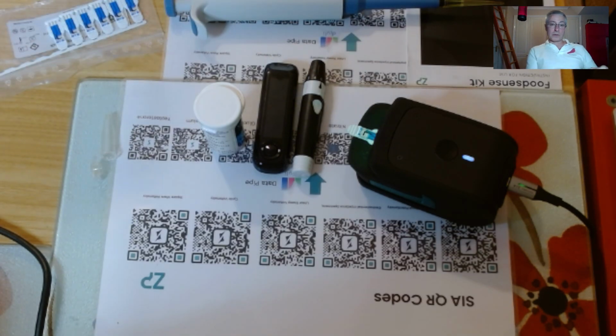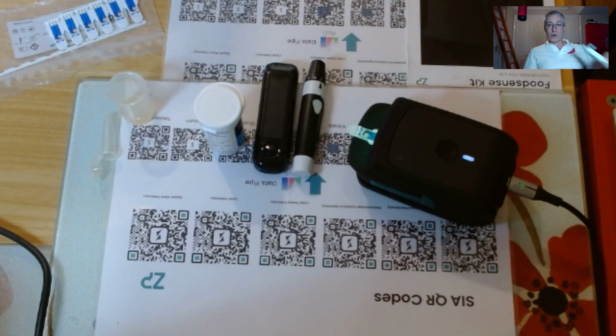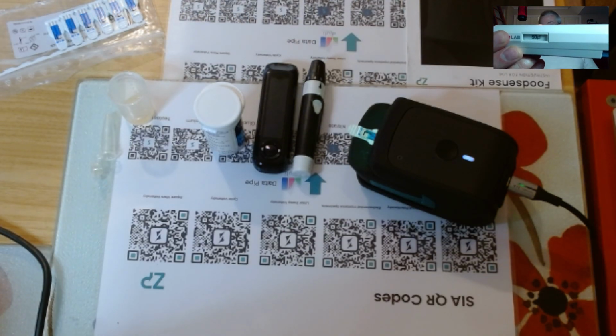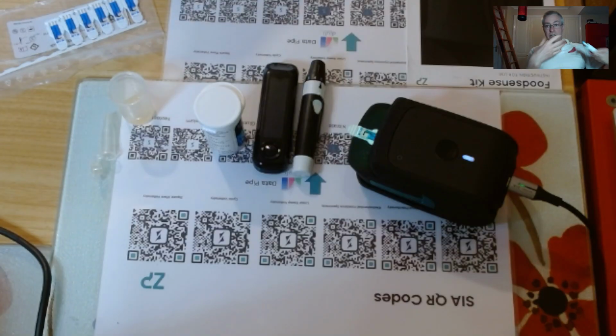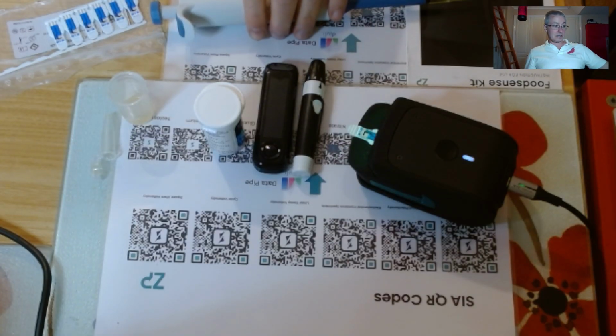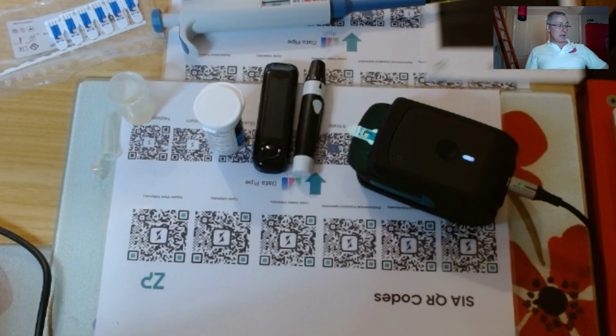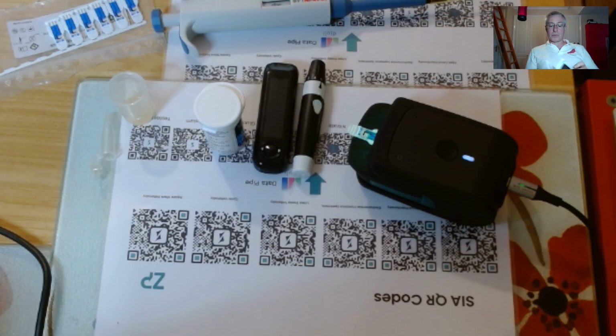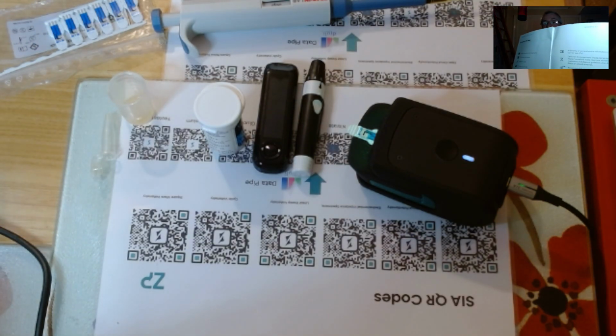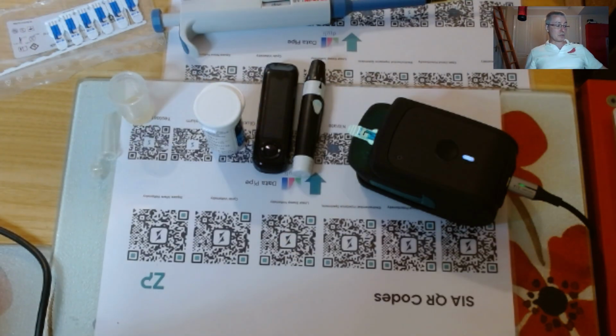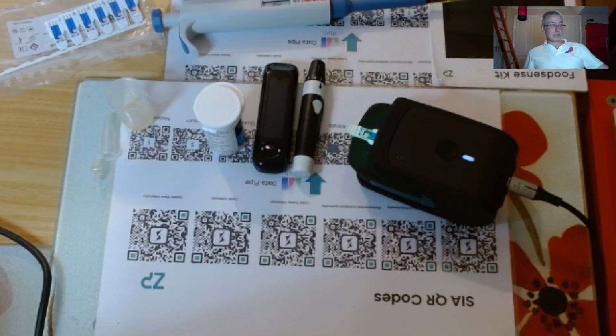So maybe, when somebody's trying to test something hot, if you put it in a little vial like this and just leave it a minute or so, it will soon be at room temperature. Liquids, especially 50 microliters, will not hold on to their temperature that much. They're a very small object with quite a large surface area, so they'll lose their heat quite quickly. But the quick answer to your question is, in accordance with the manual, which is very thin and very comprehensive, the system should be at 20 to 28 degrees Celsius. I'm sorry, it's a bit bright there. The sample should really be in that temperature range as well. But honestly, you should find that a 50 microliter sample is a very small drop.